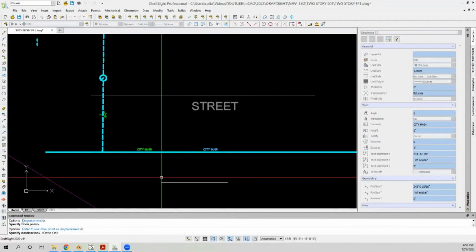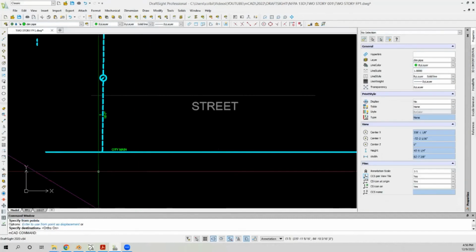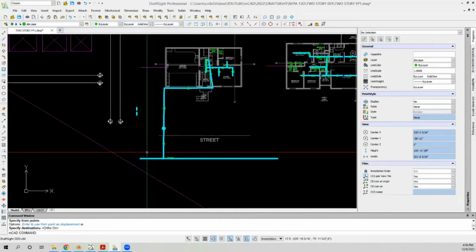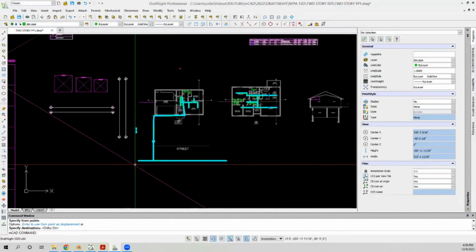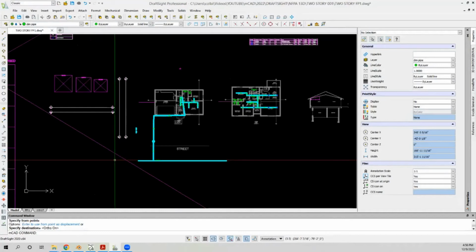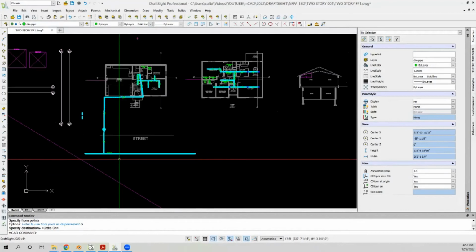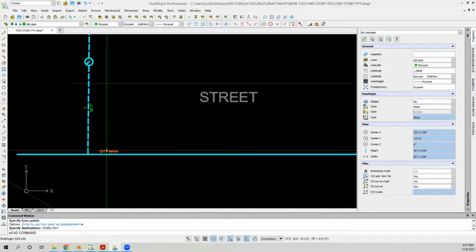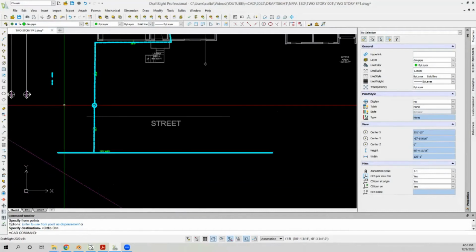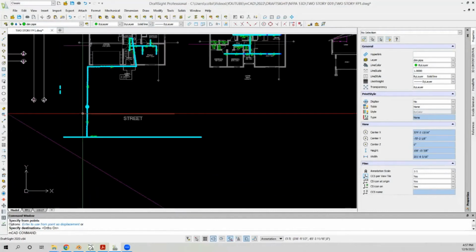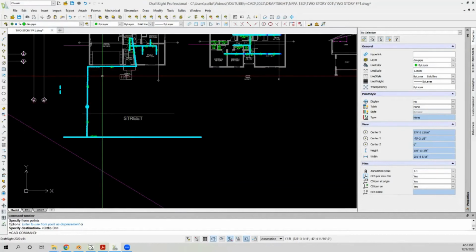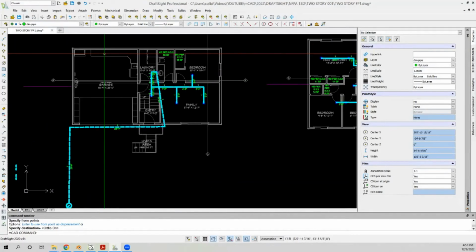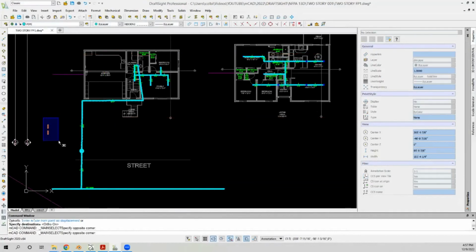If this was a 13 or even a 13R, I'd be showing the hydrant rate. It's only like, I think, one driveway down across the street and one driveway down. It's pretty close. I could probably show that on here too if I wanted, but I normally don't go to that extent on 13D. I don't believe it's required on the 13D checklist. I should have had that to show you too.